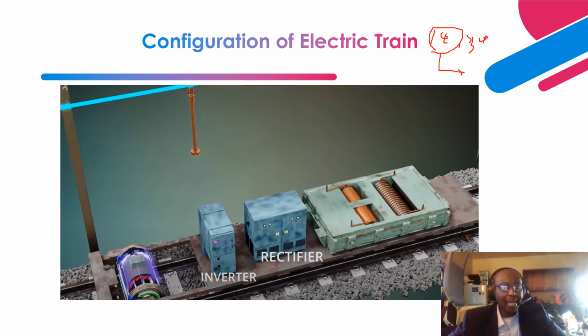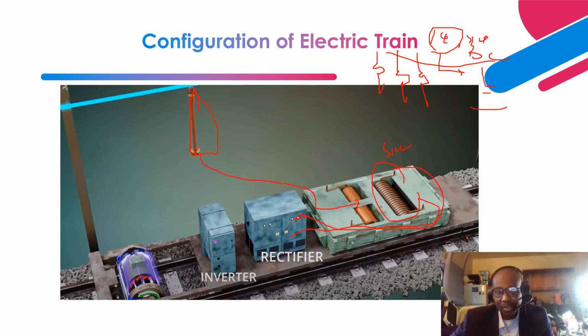So I come in here with a single phase, then I feed it to the primary side of my transformer, then I step it down to 3 kV over here. Then from there, I feed my rectifier. The rectifier basically has diodes that rectify the AC sinusoidal voltage to a DC voltage equivalent. So this should be a DC bus that has a capacitor to help keep the DC voltage before it comes to an inverter, which inverts the voltage to the AC equivalent before providing that three-phase voltage to the induction motor.